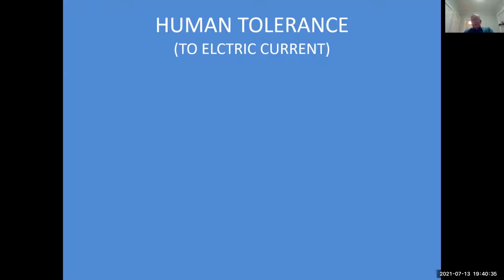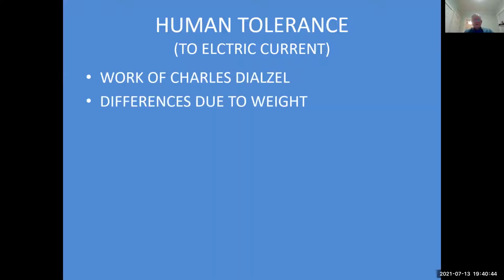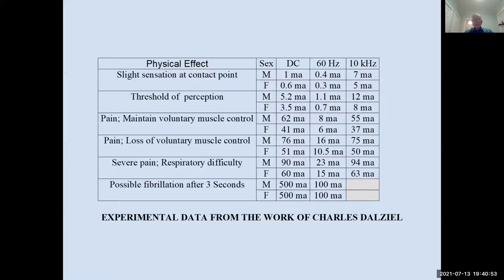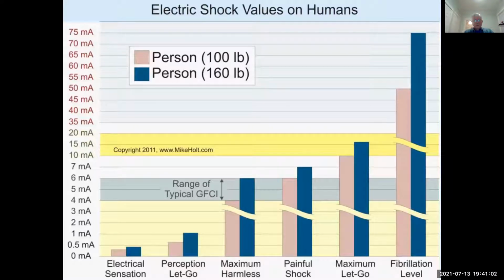The importance of grounding is the various levels of tolerance to electric current. Charles Dalziel, who also was the father of the ground fault circuit interrupter, did many studies, found differences due to weight, and there's overlap between the reactions due to the weight of people. He tabulated it, broke it down by male, female, DC, 60 hertz, 10 kilohertz. But a better illustration would be presenting it this way, because if you look at it, you'll see that the maximum harmless for a person who's 160 pounds is going to be at the painful shock level for someone who's only 100 pounds. So one of the reasons the Class A GFCIs that you have in your house have a 4 milliamp to 6 milliamp trip range is that they have to trip anything over 6 and stay connected anything under 4 milliamps.